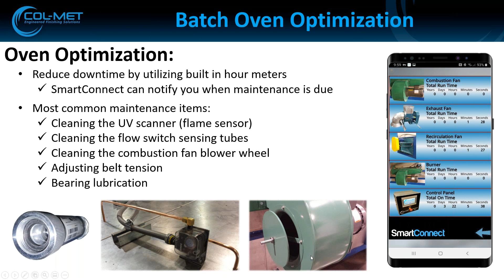Another thing we see, I guess you wouldn't necessarily call it common, but we do see it on occasion, is poor housekeeping. People forget about the stuff that they can't see, like the things on top of the oven. It's out of sight, out of mind. But it's important to get up there and occasionally clean that stuff up. Maybe whenever you're up there adjusting belt tension, take a broom and a shop vac up there. Just don't leave it up there like the picture shows on the right. But it's especially important to keep the area around the burner clean, because if the blower wheel gets dirty and starts pulling in dust and powder and things of that nature, it's eventually going to clog up the burner, and that just leads to more fuel consumption. And once the burner gets to the point of no return, it basically has to be replaced. So that gets pretty expensive.